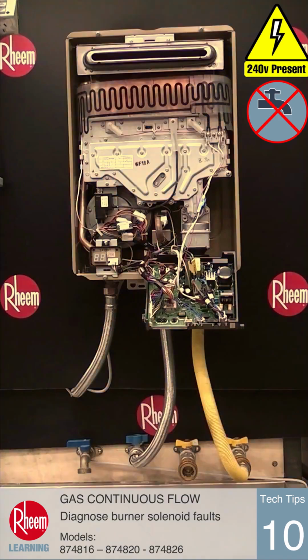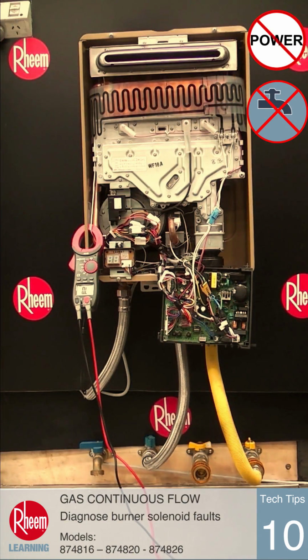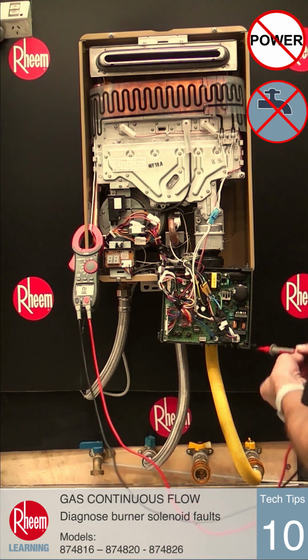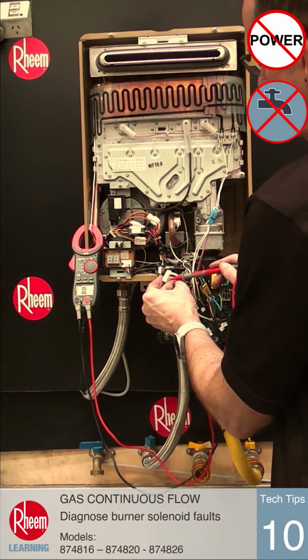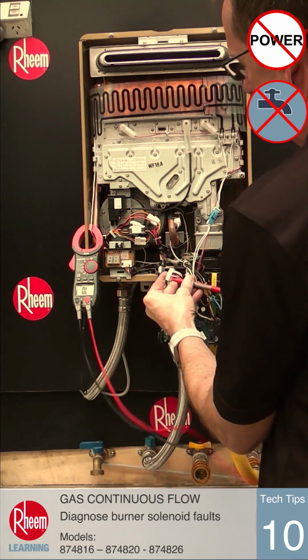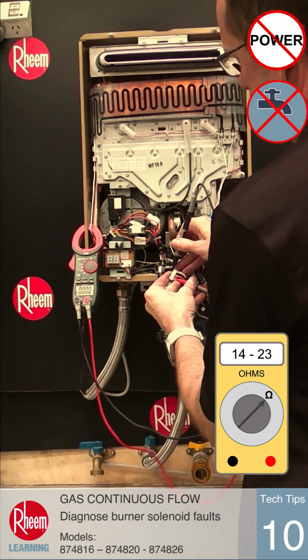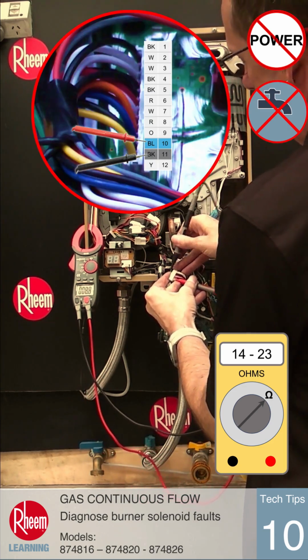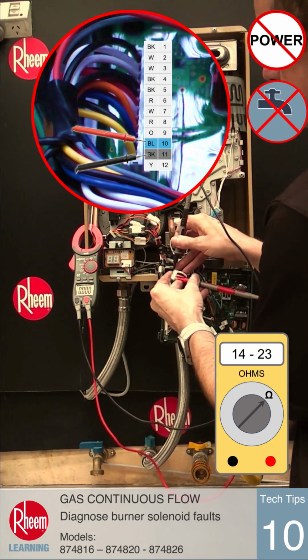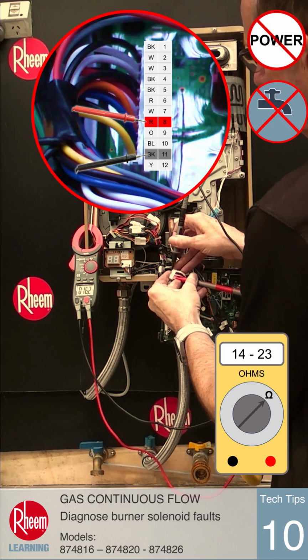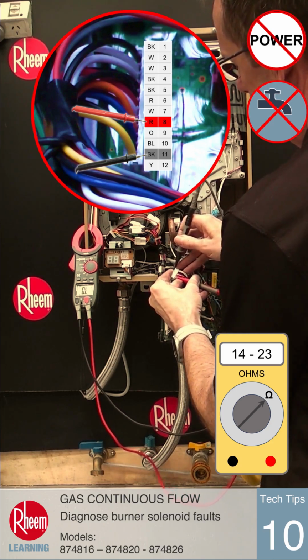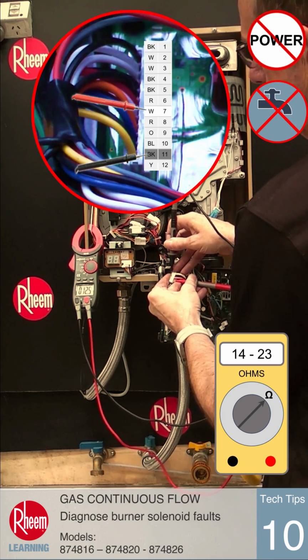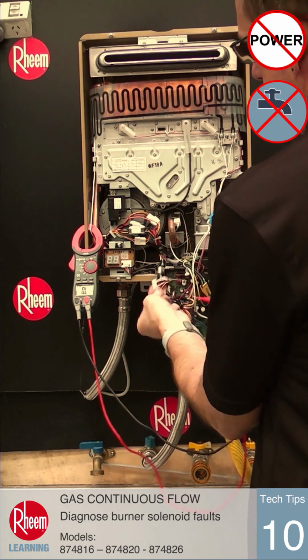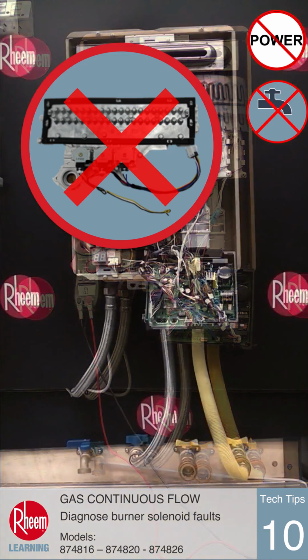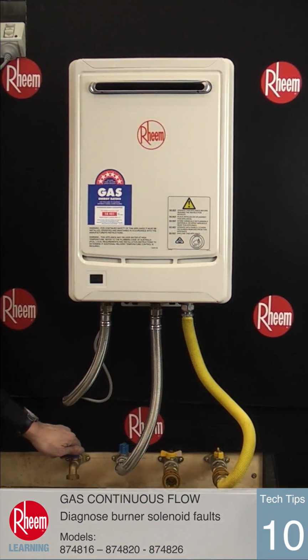If the voltages are good, turn off the power and remove connector I from the PCB, and then use the test meter to measure ohms for each of the solenoids in turn. The reading for each solenoid should be between 14 and 23 ohms. Solenoid 1 is measured between pin 11 black and pin 10 blue. Solenoid 2 is measured between pin 11 black and pin 8 red. Solenoid 3 is between pin 11 black and pin 7 white. If any of these are open circuit or out of range, the lower burner assembly has a faulty solenoid and should be replaced.